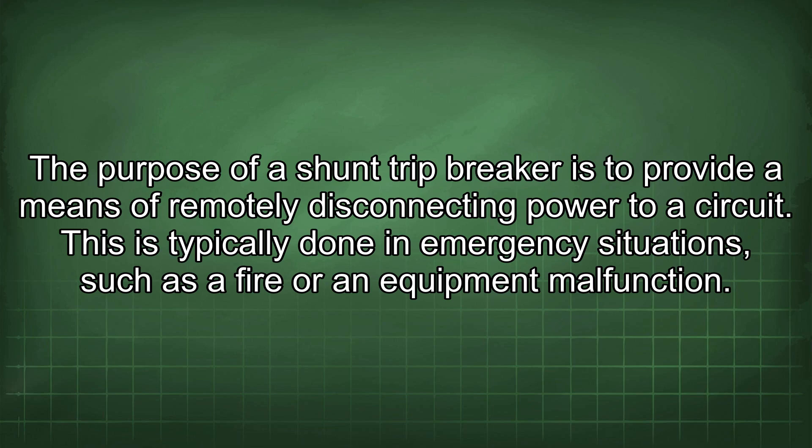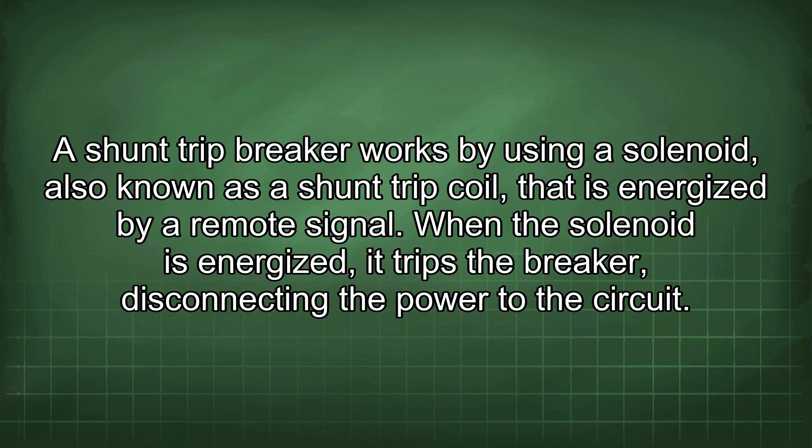This is typically done in emergency situations such as a fire or an equipment malfunction. A shunt trip breaker works by using a solenoid, also known as a shunt trip coil, that is energized by a remote signal.